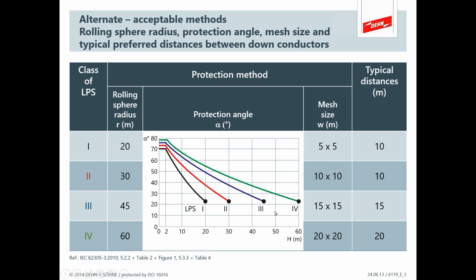If you apply a table like this, say for average risk class 3, you can predict a rolling sphere angle based on your structure's height. If my tower is 40 meters, like that TV antenna next to the sycamore tree that got struck, maybe it was around a 40 meter tower, that's about 120 feet, pretty tall, but let's just pick a number. A 40 meter height tells me my angle needs to be about 27 degrees, an angle of declination around that area.